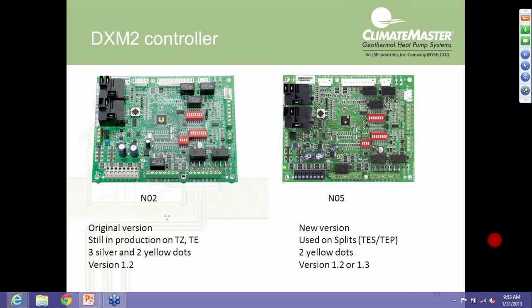Next up, right after this slide, we're going to get into the more technical side. Along with that, I want to point out that with the DXM2 control board, there are two versions: the N02 and the N05, and we're moving more towards the N05. The N05 has a slightly bigger microprocessor on it. Visually, you can also tell the difference because the N05 will have two jumpers. We're going to talk about the AO2 jumper in the technical section, right here underneath where I've got the highlighter. And then we now also have an AO1 jumper.